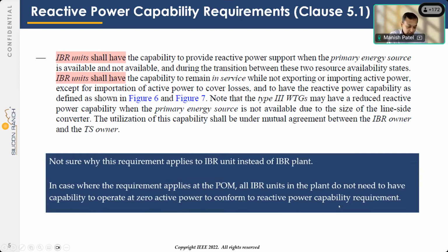Somewhere in that clause, and this is what I mentioned earlier that someone brought to my attention, it says that IBR unit shall have the capability to provide reactive power when primary energy source is available and not available. So this is to emphasize that, say, the sun went down, primary energy source is not available. If it's a solar plant, then the units in the plant shall have capability to provide reactive power, right? The second statement again emphasizes IBR units shall have the capability to remain in service while not exporting or importing active power except for importation of active power to cover losses.